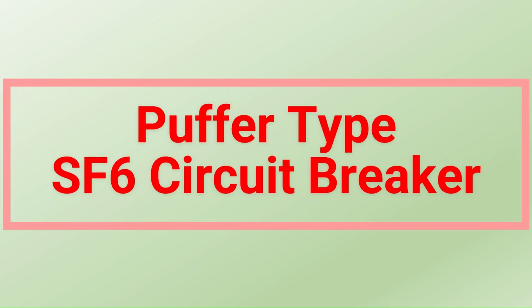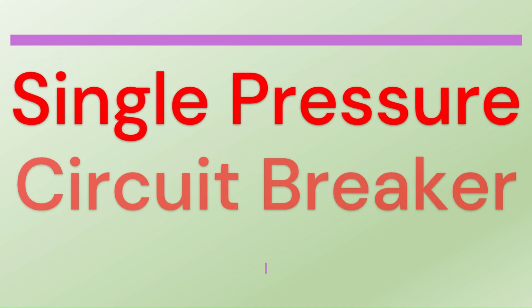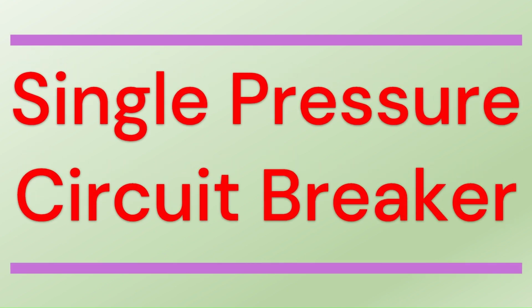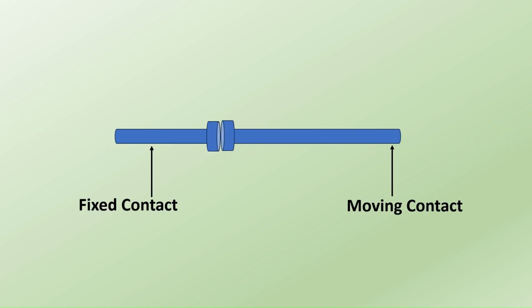Now we will discuss the puffer type SF6 circuit breaker. The puffer type SF6 circuit breaker is also called a single pressure type circuit breaker. In this type of circuit breaker, two contacts are made available like any other type of circuit breaker. One is a fixed contact and the other is a moving contact. A moving cylinder is linked with the moving contact so that at the time of opening of the contact, the moving cylinder will also move along with the moving contact.